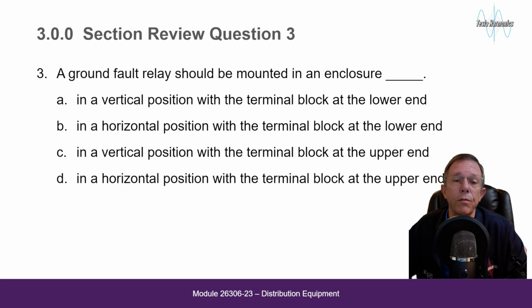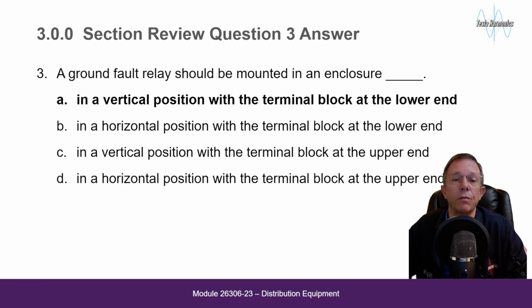A ground fault relay should be mounted in an enclosure in a vertical position with the terminal block at the lower end, in a horizontal position with the terminal block at the lower end, in a vertical position with the terminal block at the upper end, or in a horizontal position with the terminal block at the upper end. That's going to be A, in a vertical position with the terminal block at the lower end.